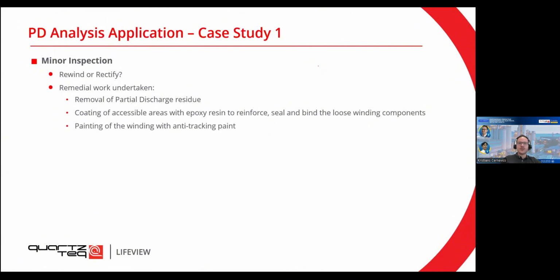So now the question is, do we need to rewind it completely, or maybe we can do minor repairs? What was decided, based on the magnitude of these first measurements, was that it's not that critical yet. However, some remedial work needs to be done. So what was done was, like I told you before, that for some of these partial discharges on the surface, you can just clean it, which should decrease the amount of partial discharges. It was then coated with epoxy resin to reinforce some of these loose winding components. And it was also painted with anti-tracking paint, to decrease it even further after it was cleaned.